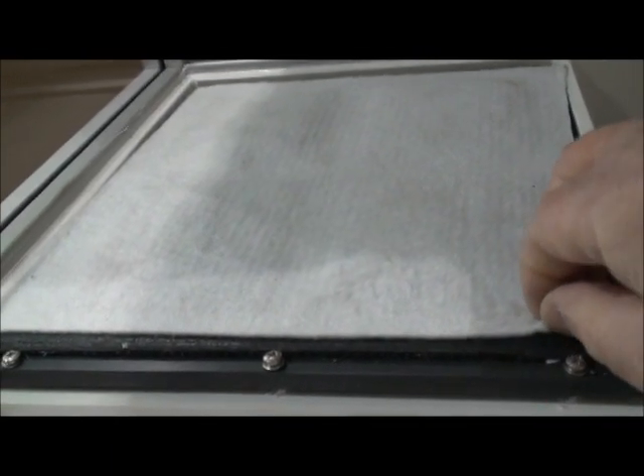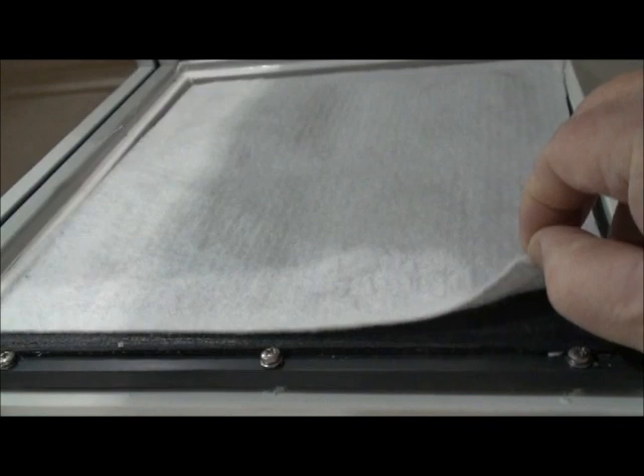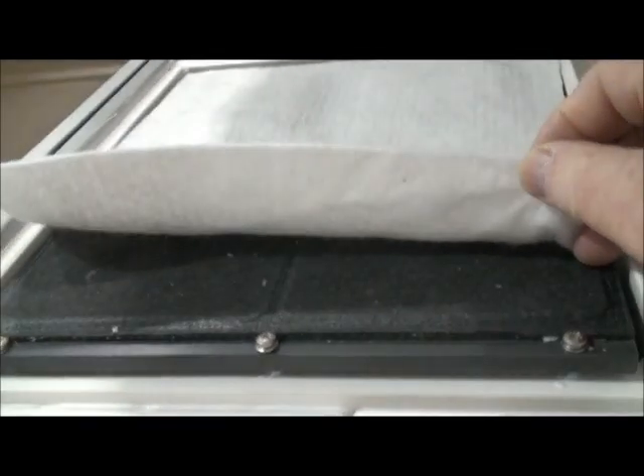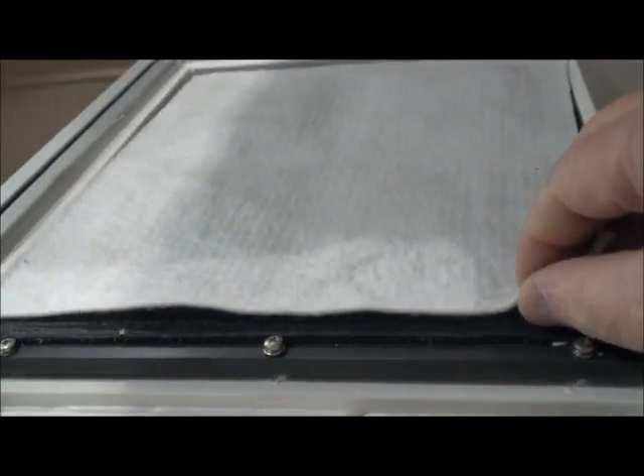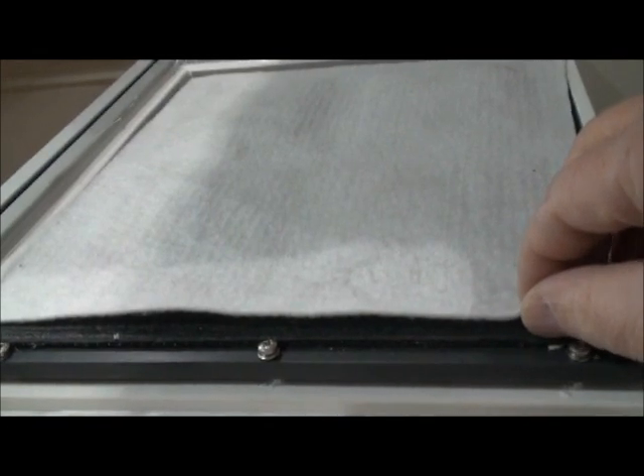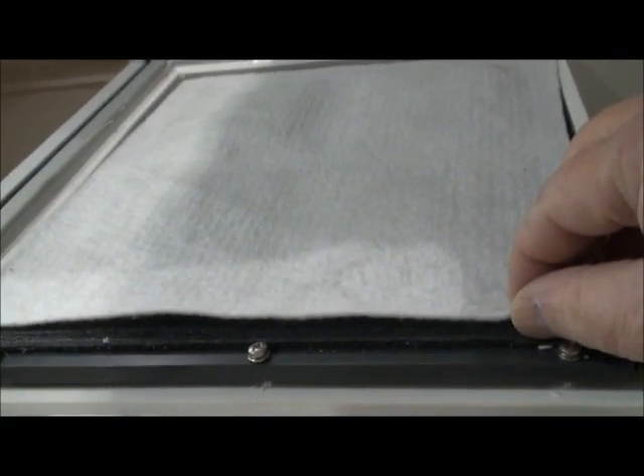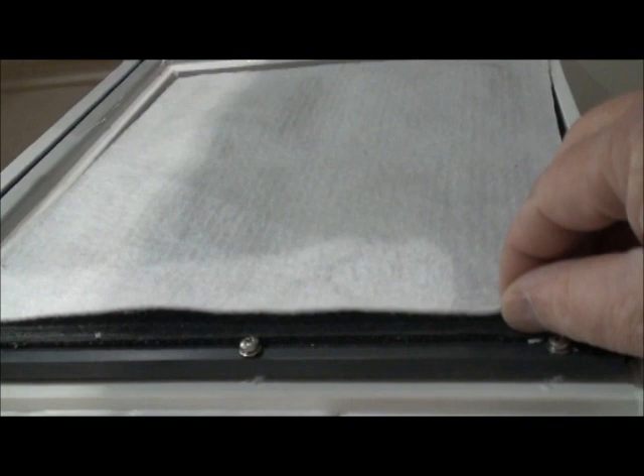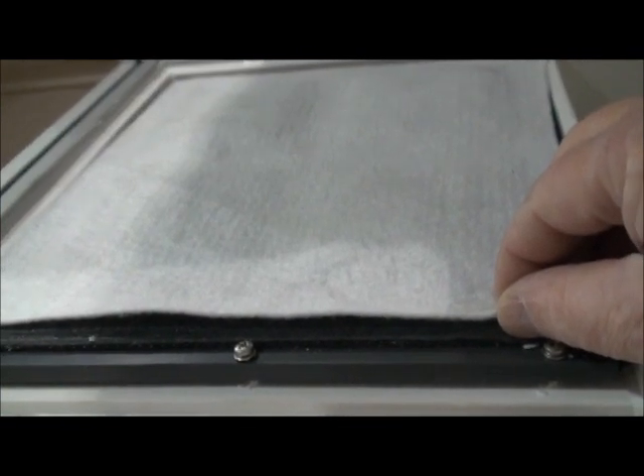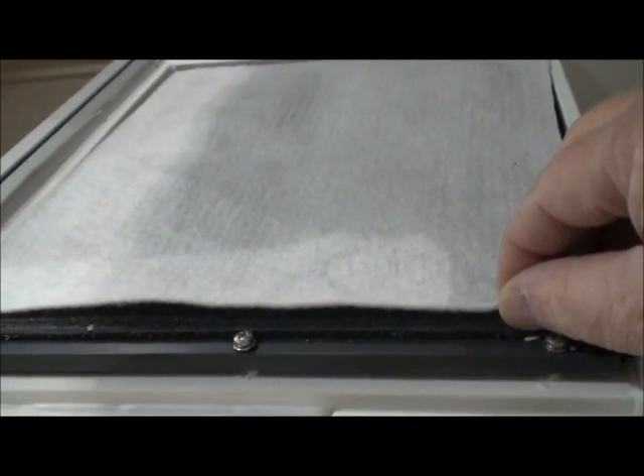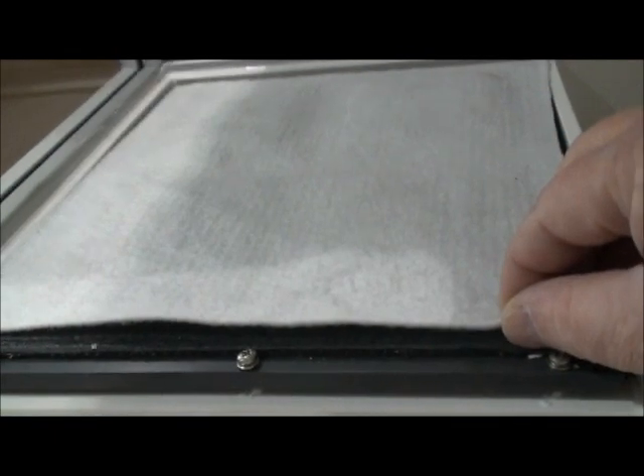In the corner, you'll see, lift the cover off. There's the pre-filter, which is designed to protect the main filter from any dust particles and glue residue. This is an anti-static material, and it will take particulate sizes down to 5 microns. This needs to be replaced frequently to keep the efficiency of the purging at the set level.